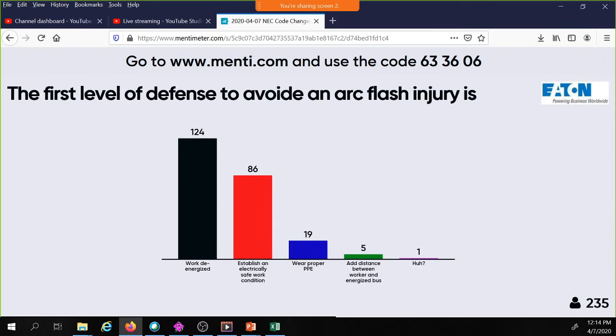The first level of defense to avoid an arc flash injury is working de-energized, establishing an electrically safe work condition, wear proper PPE, add distance between worker and energized bus.